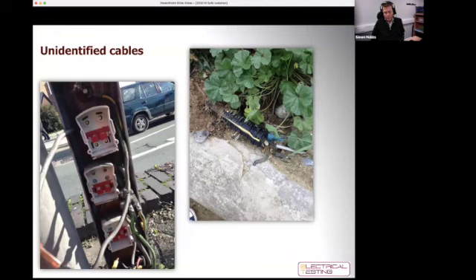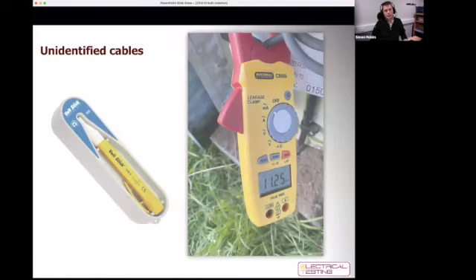Where there is uncertainty regarding the isolation when removing unidentified cables or proving dead an unused cable, where there's not enough conductor exposed to enable the use of test probes, and remember isolation can only be proved by direct contact with a test lamp and the like, we have to assume that all conductors are live until they are positively proved dead. So what that means is that any work that's going to be carried out on an unidentified cable should employ live working techniques until all of the conductors are proved dead and isolated. So it's quite a big step to move to there with unidentified cables.